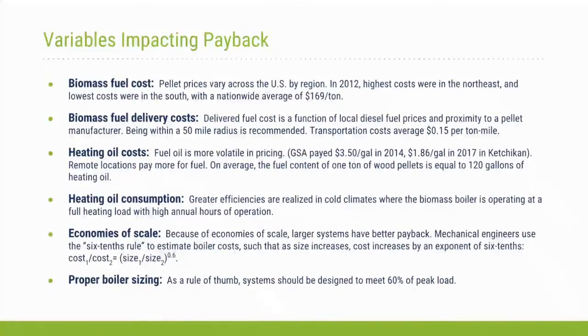Just to review the variables that affect the payback and overall economics of the system: biomass fuel cost is very important. In remote areas, pellet manufacturers are limited, and in some cases the pellet manufacturers and pellet users have a codependent relationship—people won't necessarily put in a pellet mill unless they know they've got pellet projects, and vice versa. That's key to keeping cost in line.